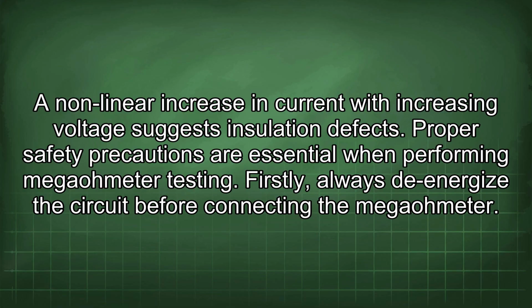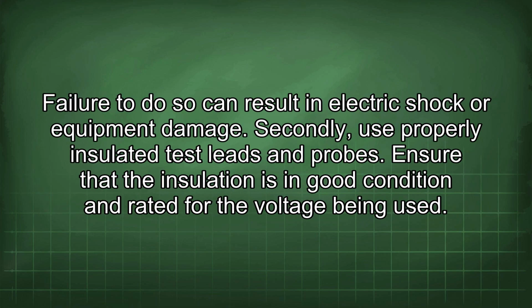Proper safety precautions are essential when performing megaohmeter testing. Firstly, always de-energize the circuit before connecting the megaohmeter. Failure to do so can result in electric shock or equipment damage. Secondly, use properly insulated test leads and probes.